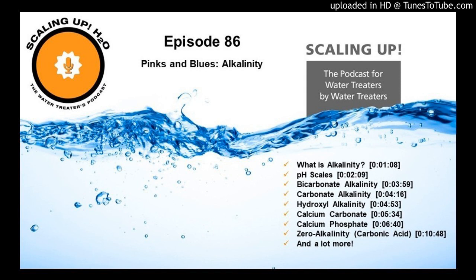Now you might be wondering what happens below 4.3. Well, folks, that's where we have the absence of alkalinity, and that's where carbonic acid is. So now looking at boilers, especially condensate lines, if you get a pH below 4.3, you've got carbonic acid. And if you've ever seen a condensate line that has been attacked with carbonic acid, it looks like an inchworm has just plowed its way through the bottom. And it's always going to be at the bottom of the pipe because that's where the water is. That's where the condensate is.